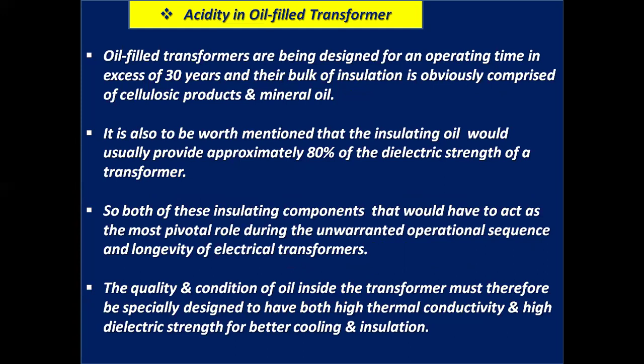Acidity in oil-filled transformer. Oil-filled transformers are designed for an operating time in excess of 30 years, and their bulk of insulation is obviously comprised of cellulosic products and mineral oil. It is also to be mentioned that the insulating oil usually provides approximately 80% of the dielectric strength of a transformer.